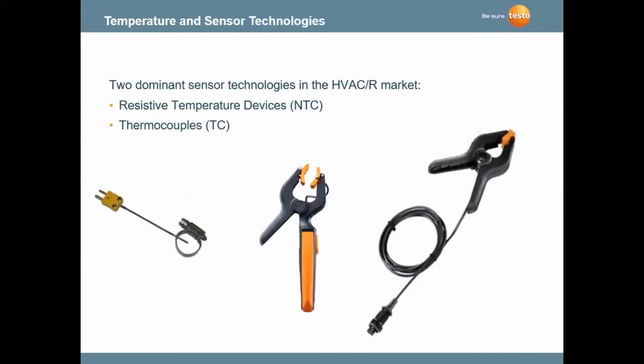With pipe clamp probes, there are two different types of sensors that we use. Testo uses what we call NTC, which is a temperature resistance type sensor, and a thermocouple, which is two dissimilar metals joined together, where we measure the voltage change. And NTC stands for negative temperature coefficient.